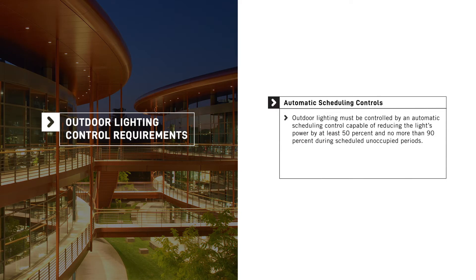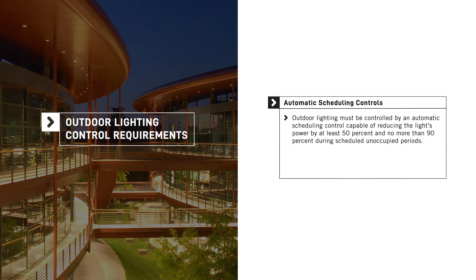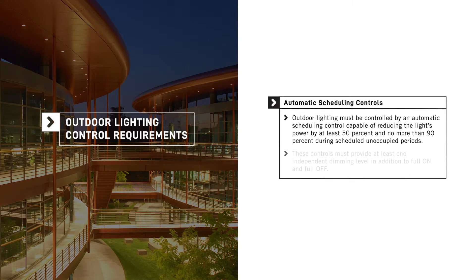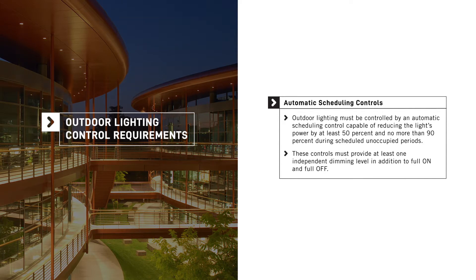All outdoor lighting must be controlled by an automatic scheduling control capable of reducing the light's power by at least 50 and no more than 90 percent during scheduled unoccupied periods. These automatic scheduling controls must provide at least one independent dimming level, in addition to full-on and full-off.